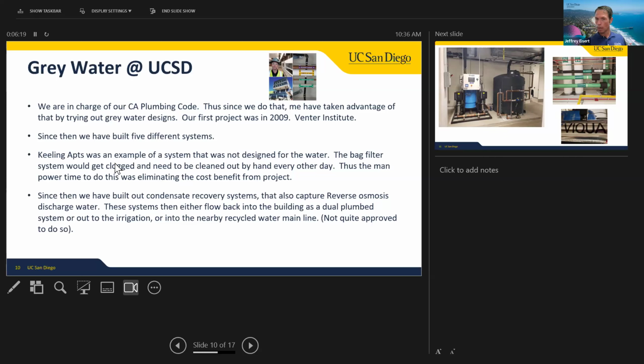Well, the water didn't turn out like that at all. It turned out to have a lot of hair and sand in it, but not funky, and it didn't smell bad. But the treatment design down in the mechanical room used filters almost like these coffee filter socks, and the sand and hair went right into them and jammed the whole thing up. The water was supposed to flow through. Nope. So housing had to use all their maintenance staff just to keep cleaning these filters.